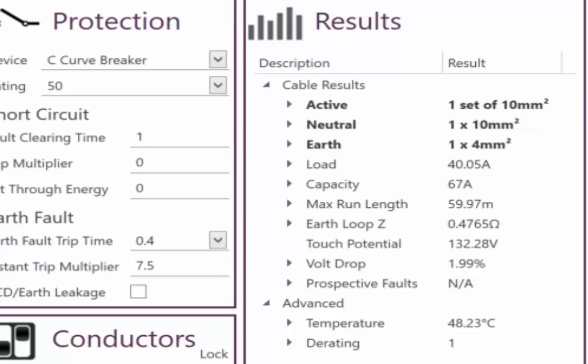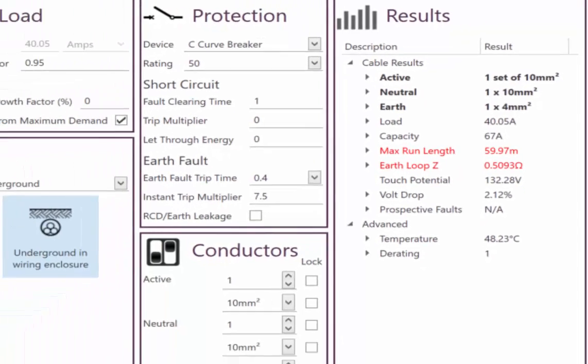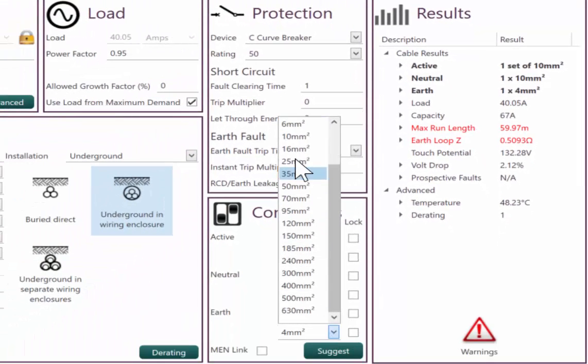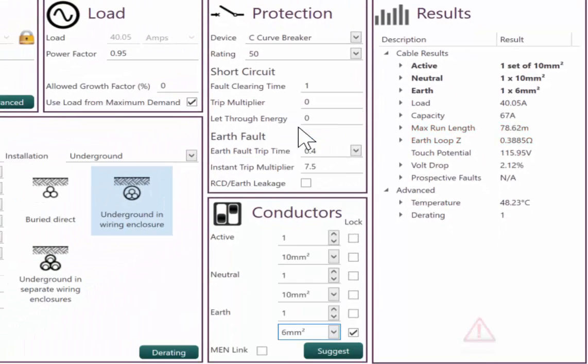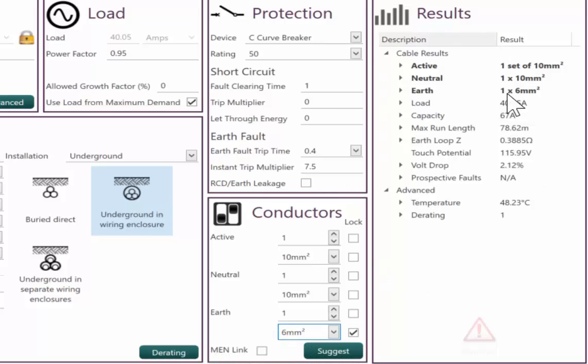Let's say for some reason, our run length was 62 meters. So we, and we just can't find two meters on site. Well, the other option is we could come in and say, okay, we're going to fit a six mil earth instead of a four mil earth. And we have now picked up the solution.